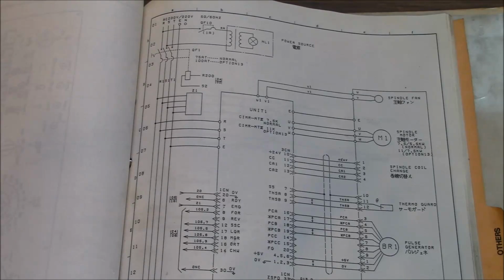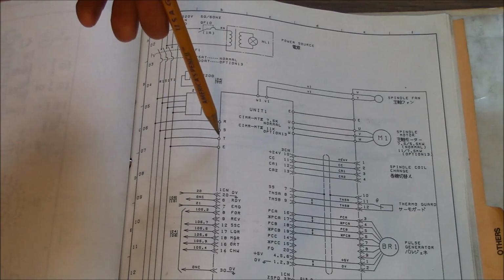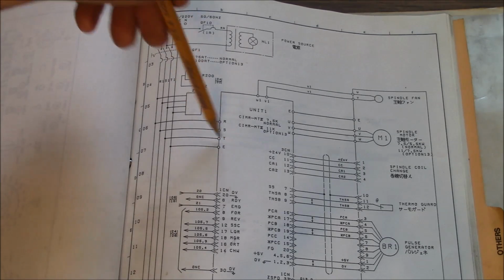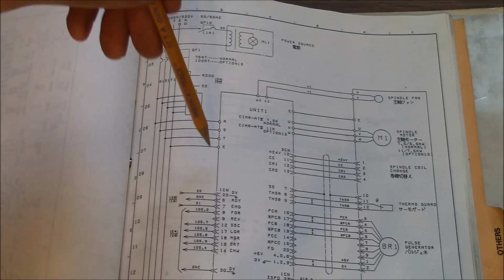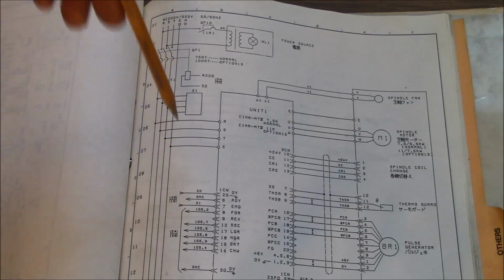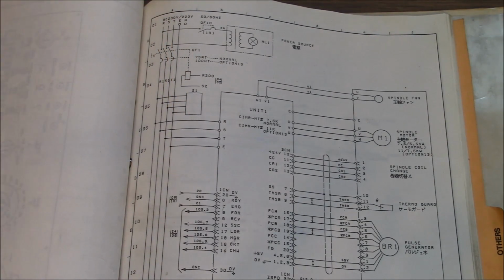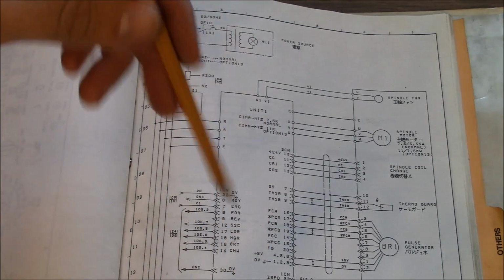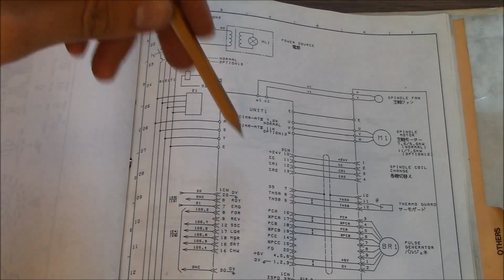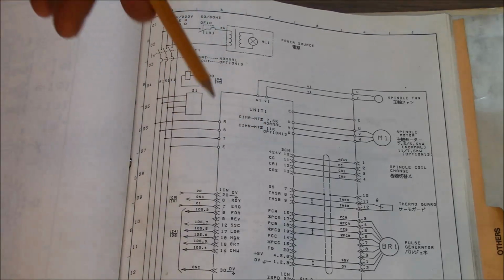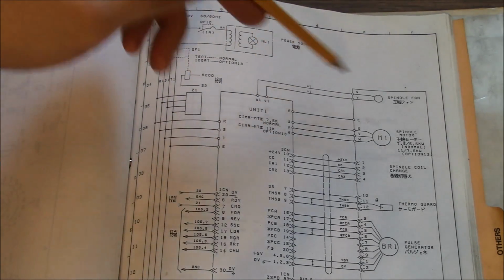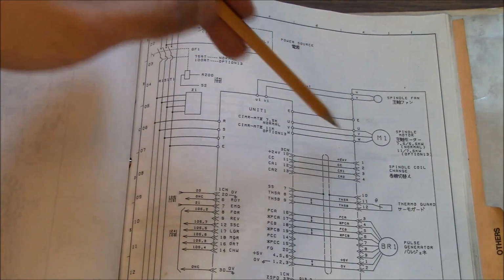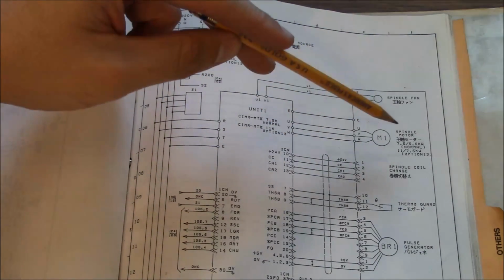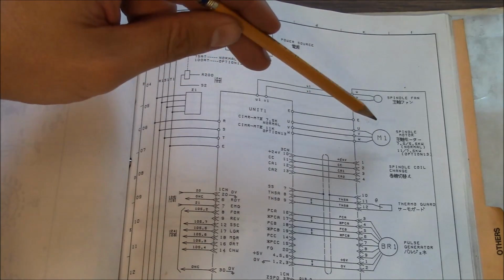So you can see all the action going on with this spindle drive. R, S, and T, and then E is the ground - this is your main power coming into the spindle drive, it comes right off the main breaker. The spindle drive has its own built-in circuit breaker, so you don't have to worry about overcurrent protection on that. These here go out to the fan. Then U, V, and W are your connections to your spindle motor.